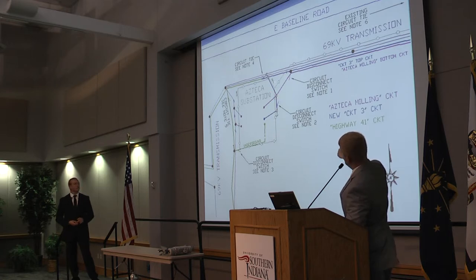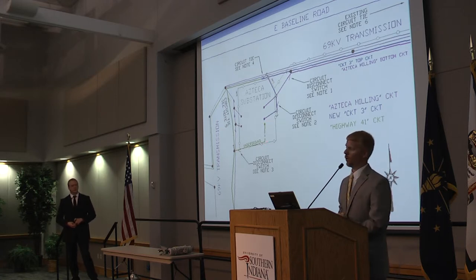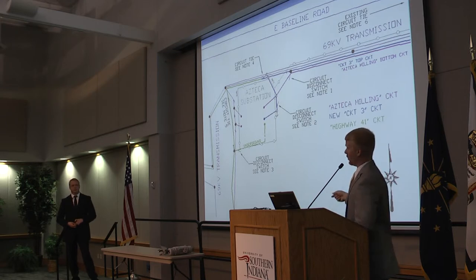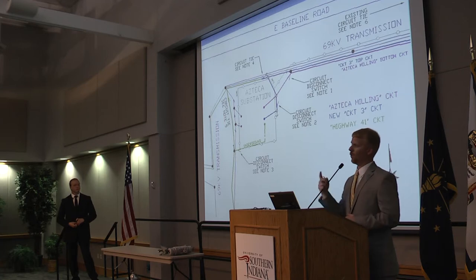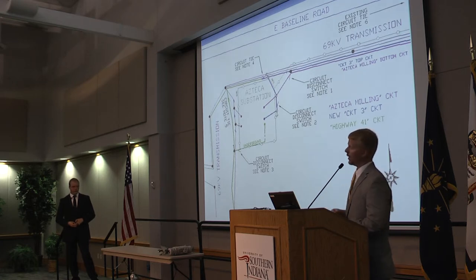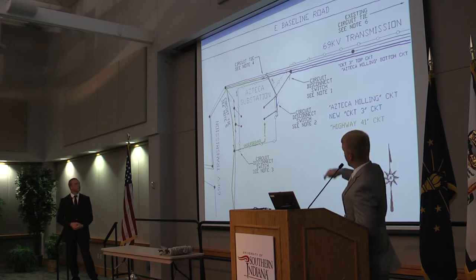This is a fence around the outside and gates, so that's the substation fence. The green, which is the Highway 41 circuit, is an underground fed circuit which comes from the voltage regulators and drops directly underground and feeds to the bottom of the substation. We had that option for our new circuit. The reason that we didn't choose that is that the terminators, which is the point where you change from the overhead cable to the underground cable, are known to go bad much quicker than the overhead circuits, and it's much harder to work on, especially in a substation because you have the grounding grid. So we prefer to go overhead, and that's why this route was chosen.